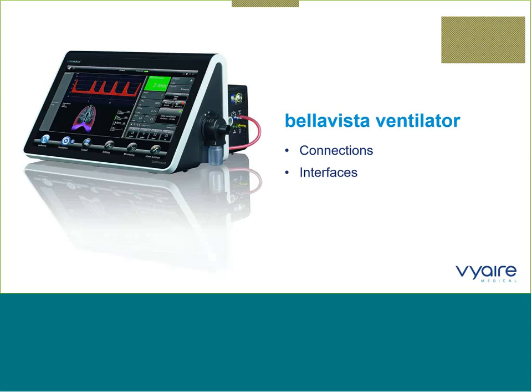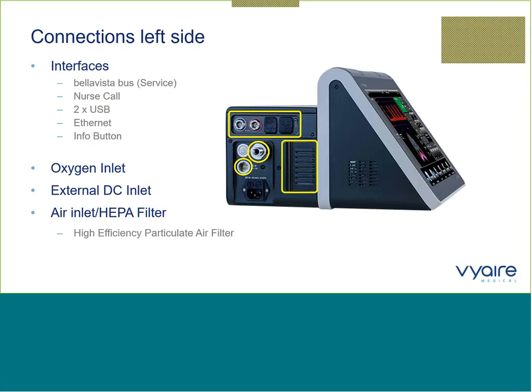We're going to start with the connections and interfaces with the Bella Vista. On the left-hand side you have the ports. You have your Bella Vista bus ports, which are primarily for service engineers. There's the nurse call control. Behind a small cover there are two USB ports, so you can potentially control your aerogen from there, or export and import data into the device. There's an Ethernet port for connectivity. The Bella Vista is offered with an array of gas inlets — that might be DISS, NIST, or AFNOR, for instance.